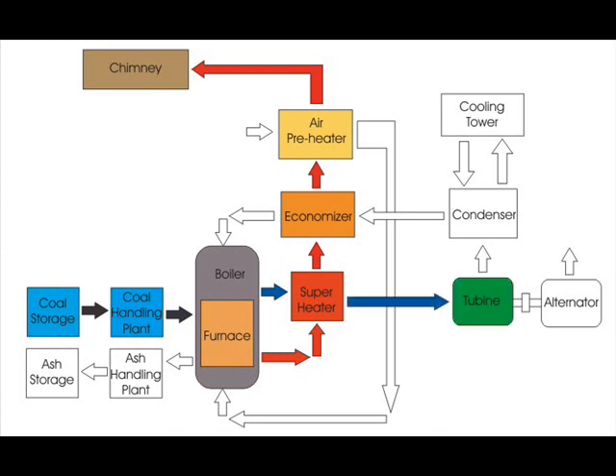The superheated steam is then delivered to the turbine. After passing through superheater, the flue gas still have some heat energy in it. Some portion of this remaining heat is utilized to heat up feed water to the boiler. Feed water passes through economizer before fed to the boiler. Here the temperature of feed water is increased by extracting heat from flue gases. After extracting heat in economizer, there is still some remaining heat in the flue gases, which can be further utilized to increase the temperature of air before feeding to the furnace for coal combustion. This air heating is done in air preheater by means of flue gases on their way to chimney.